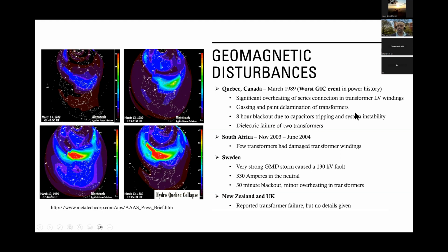So it was not just the transformers that got damaged. There were other components like capacitors. A question: do GIC type issues cause dramatic reaction, or do they just shut down? Some of the impacts are sudden, but a transformer might fail over maybe many hours or even several days later because it's already been stressed by the heating. So some of these effects from GICs may not be immediately apparent. They take time to see the impact, because transformers were designed to last for 40, 50 plus years. And if you overheat them, that severely cuts down their lifespan. So you may not see these effects for many months to come. But in the Quebec, Canada situation, the effects were quite fast. It was a very big storm, and the storm caused failures that very day.